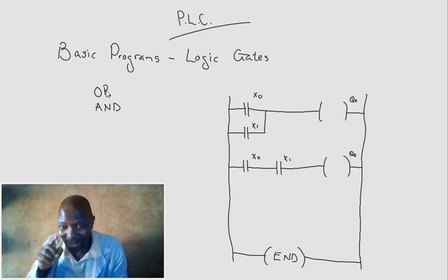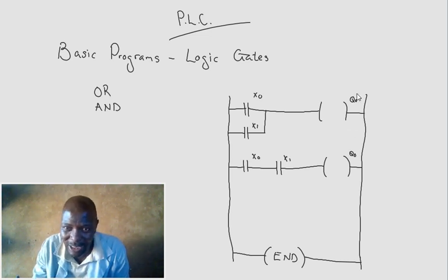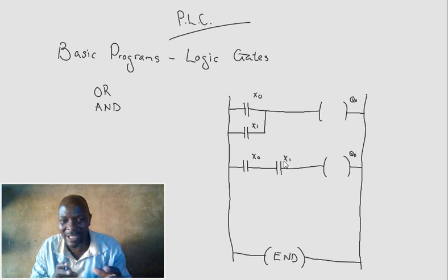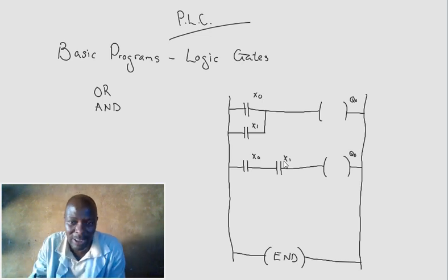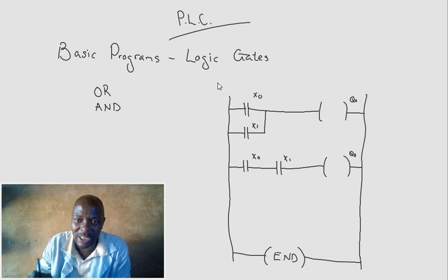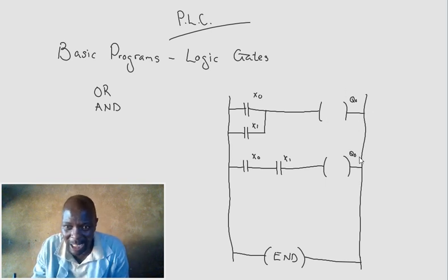Let's be very careful about some of these things. But what I'm trying to say is avoid having Q's repeated on the output, because you could have conflicting instructions trying to drive this through, and obviously if they are conflicting, the output will also be confused. So avoid, at any cost, repeating the output from different instructions, from different rungs.